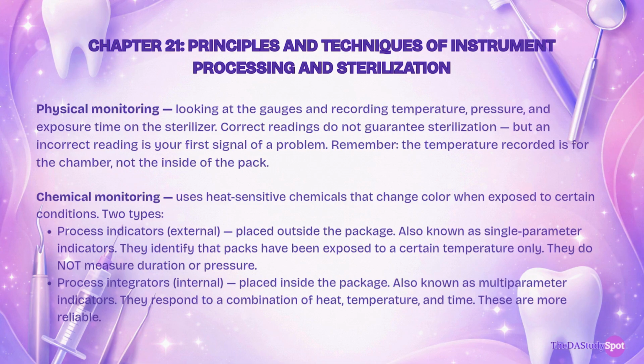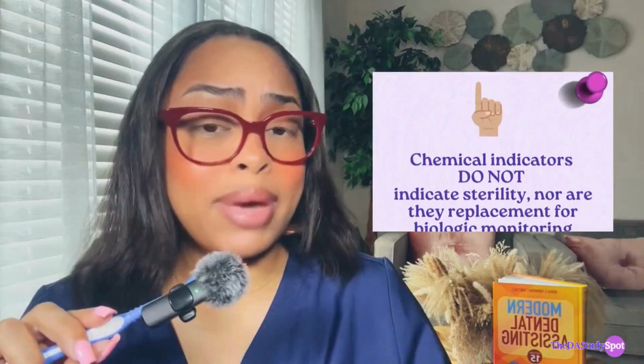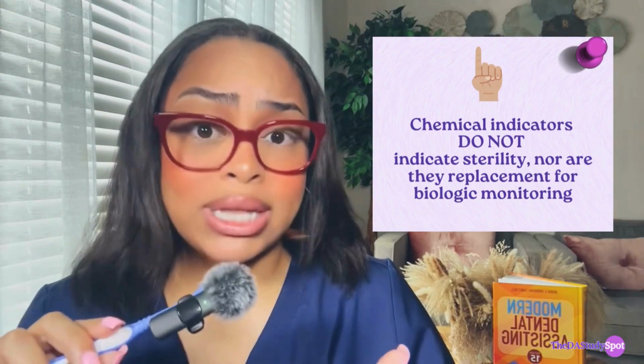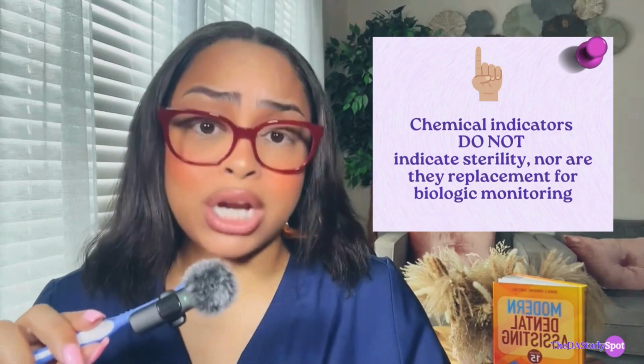The second is chemical monitoring. It uses heat-sensitive chemicals that change color when exposed to certain conditions, and there are 2 types. Process indicators that are external. They are placed outside the package. They are also known as single parameter indicators. They identify that packs have been exposed to a certain temperature only. They do not measure duration or pressure. The other, process integrators, which are internal, they are placed inside the package, and they are also known as multi-parameter indicators. They respond to a combination of heat, temperature, and time, and they are more reliable. Keep in mind that chemical indicators do not indicate sterility, and they're not a replacement for biologic monitoring.